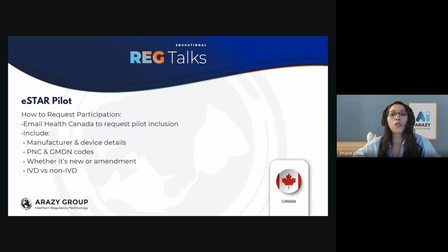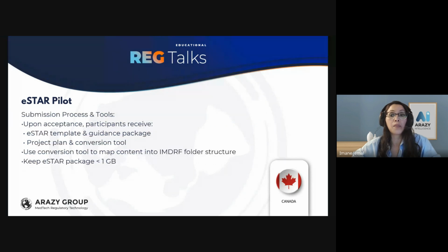Manufacturers who want to join must email Health Canada with a request to participate in the eSTAR pilot. In that message, they should include their company name, contact info, and so on, and also specify whether the device is an IVD or non-IVD. If selected, participants will get an information package that includes an eSTAR form to use, a project timeline, and the conversion tool that helps map content into the IMDRF folder structure. Health Canada also gives guidance on keeping the eSTAR file size manageable, ideally under 1 gigabyte, to reduce processing delays. So large files must be compressed and grouped wisely.